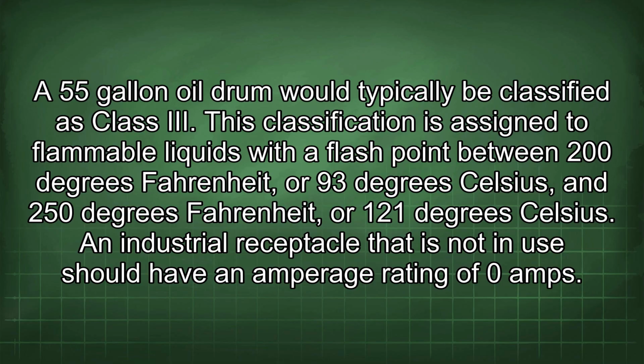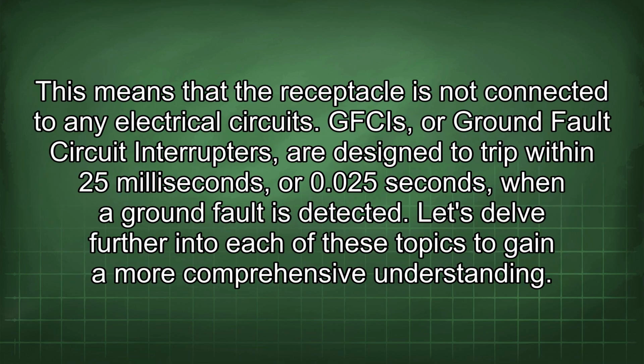An industrial receptacle that is not in use should have an amperage rating of 0 amps. This means that the receptacle is not connected to any electrical circuits. GFCIs, or ground fault circuit interrupters, are designed to trip within 25 milliseconds or 0.025 seconds when a ground fault is detected. Let's delve further into each of these topics to gain a more comprehensive understanding.